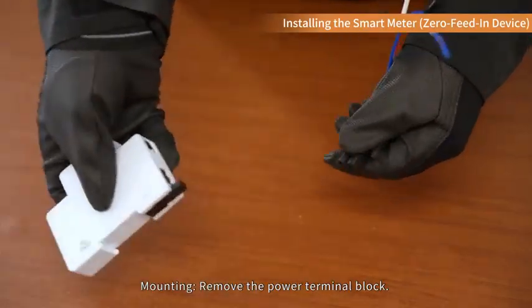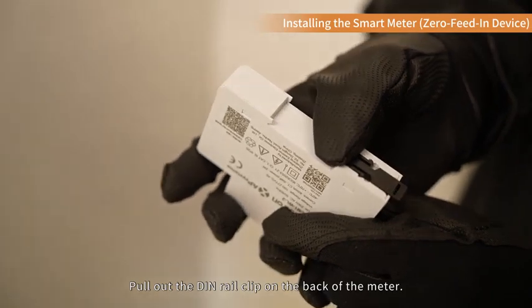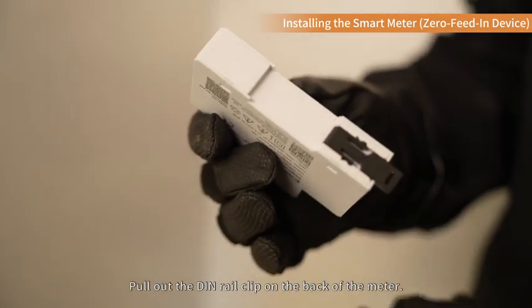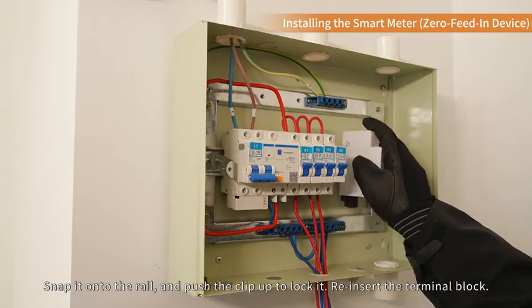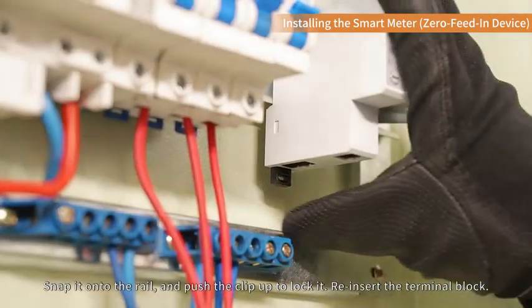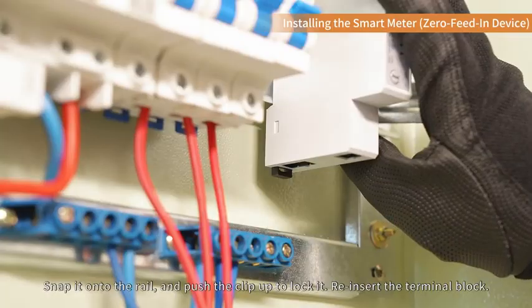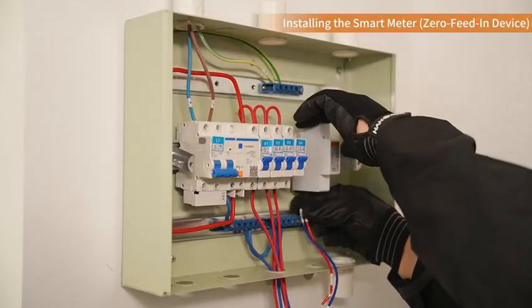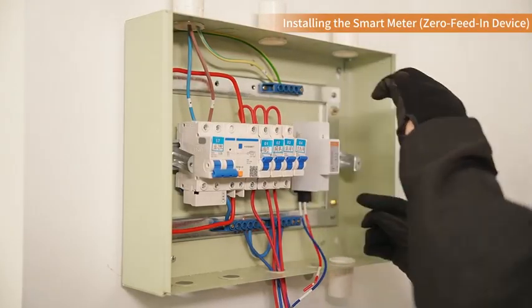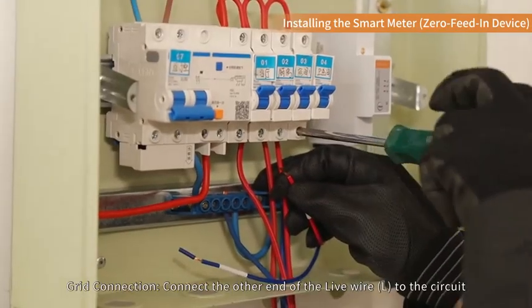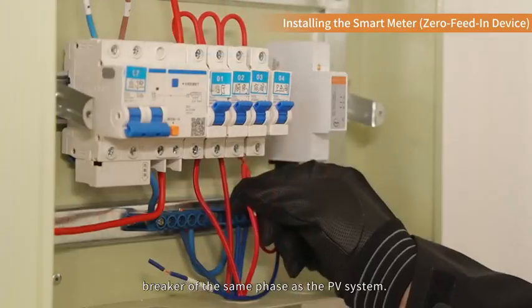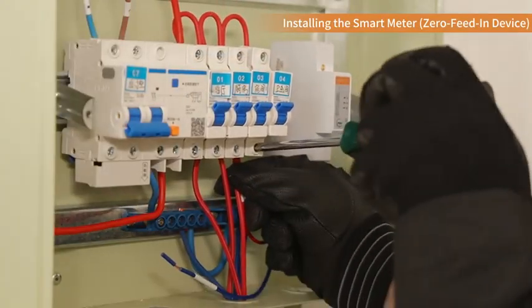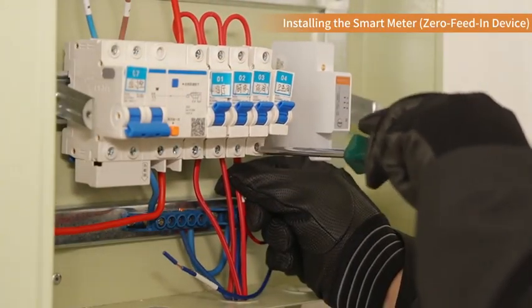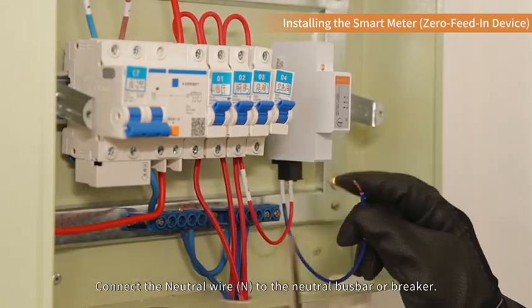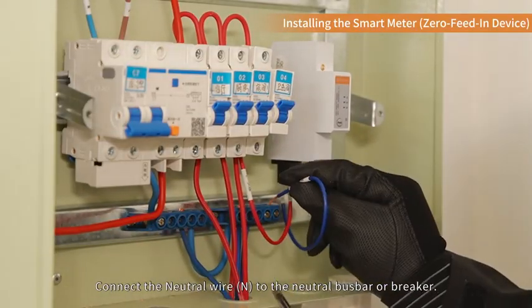Mounting: remove the power terminal block. Pull out the DIN rail clip on the back of the meter, snap it onto the rail, and push the clip up to lock it. Reinsert the terminal block. Grid connection: connect the other end of the live wire L to the circuit breaker of the same phase as the PV system. Connect the neutral wire N to the neutral busbar or breaker.